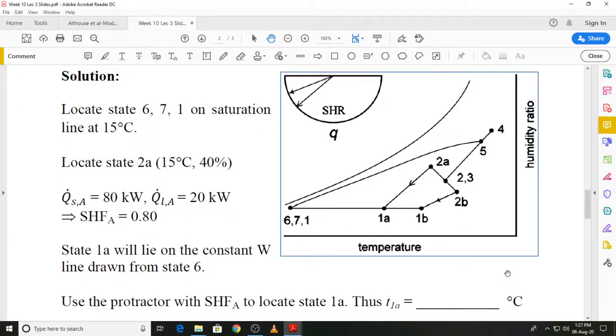You can see the schematic, the cyclic representation on the psychrometric diagram. We have the two zones, zone A and B, for which if you look at this point 6 or 7 or 1, they are all the same states, and when you refer to the schematic diagram of this arrangement, which you can refer to from the earlier lectures, you will see that this is the state at which the conditioned air leaves the cooling coil, and then that air will be reheated as per requirement of each of the zones. So for zone A you will reheat it from state 6 to state 1A, and similarly for zone B you will reheat it from state 6 to state 1B.